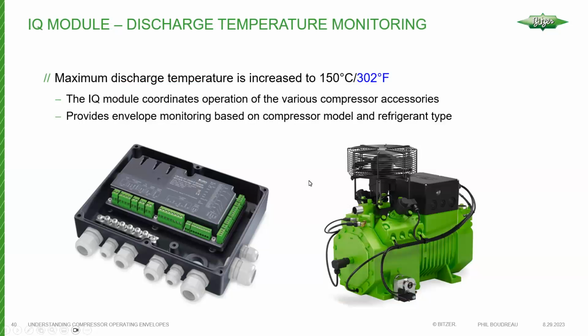Note, with the newer approach to the enhanced compressor technology, now with the IQ module, the discharge temperature is actually increased to 150 degrees C or 302 degrees Fahrenheit, which is a little more than what it was before.